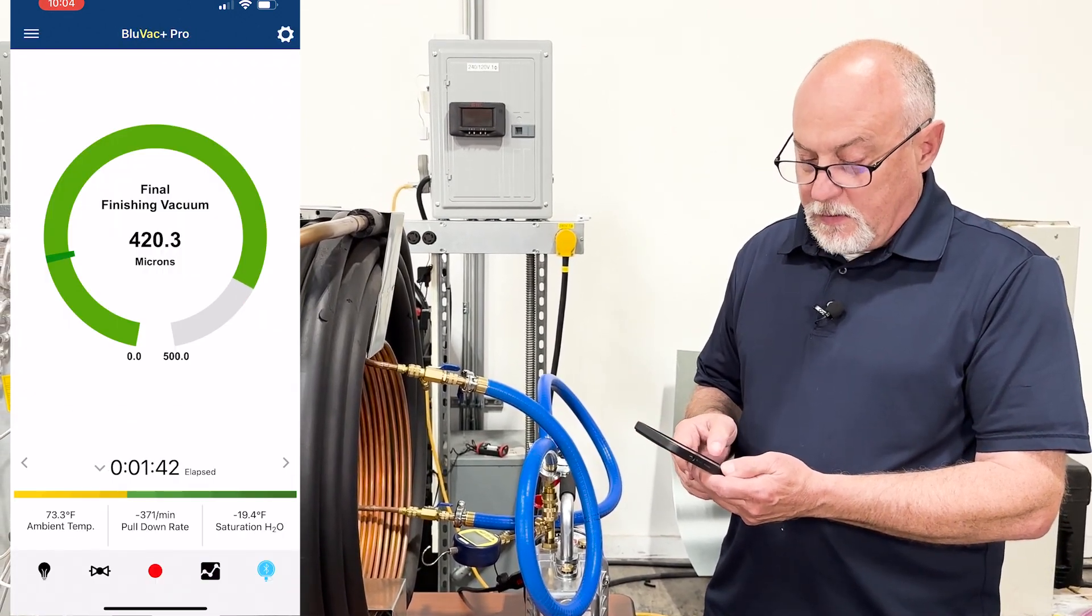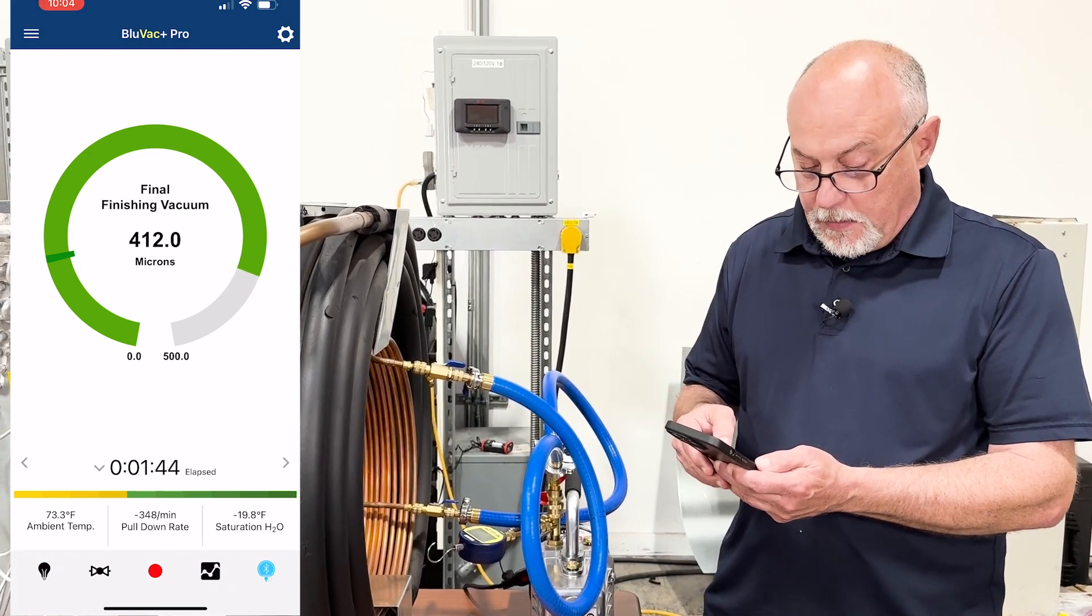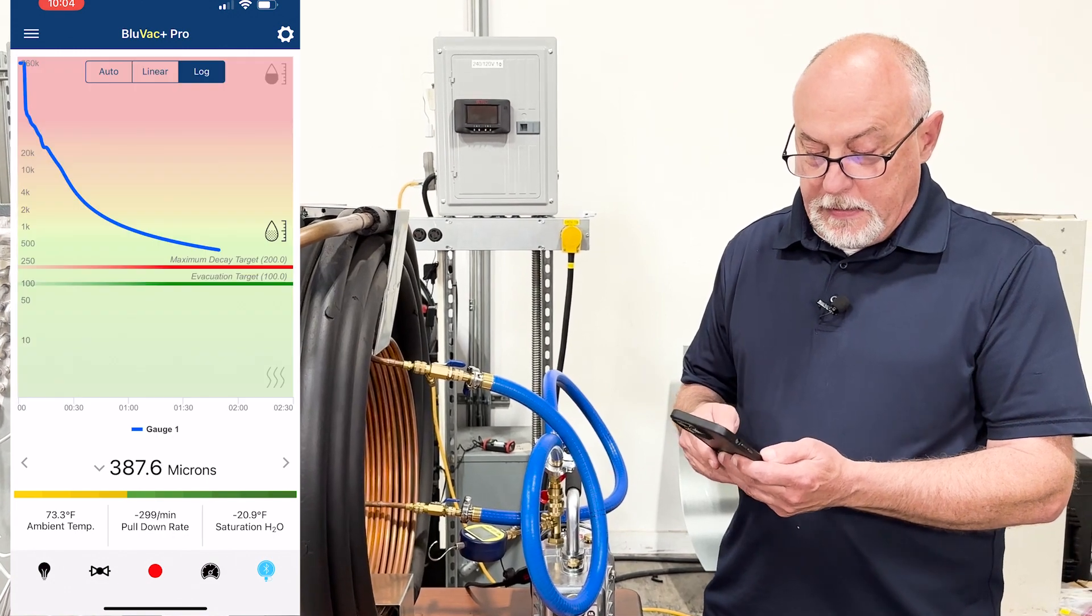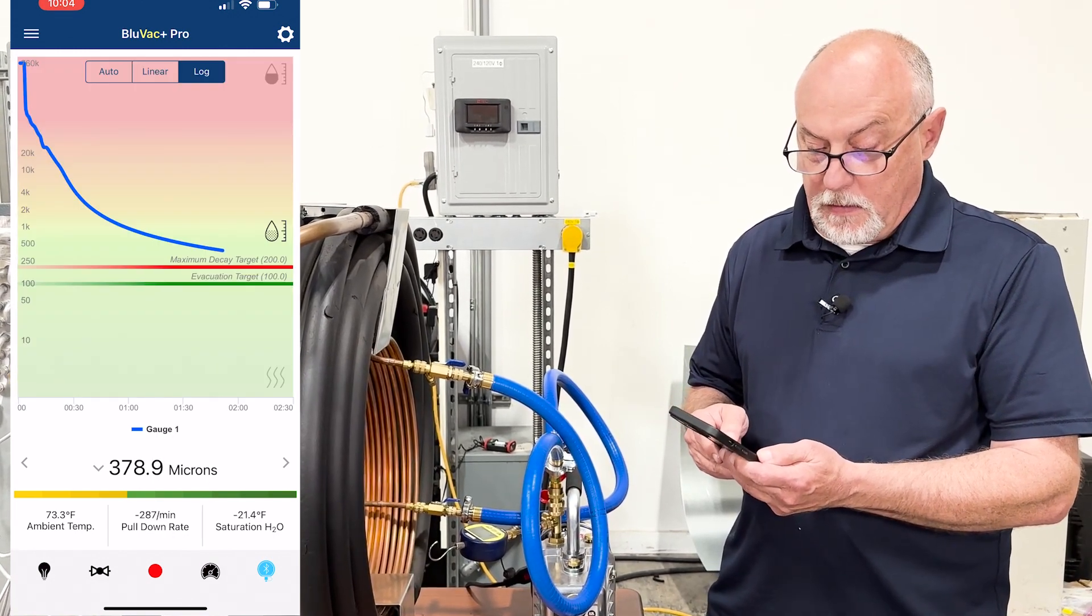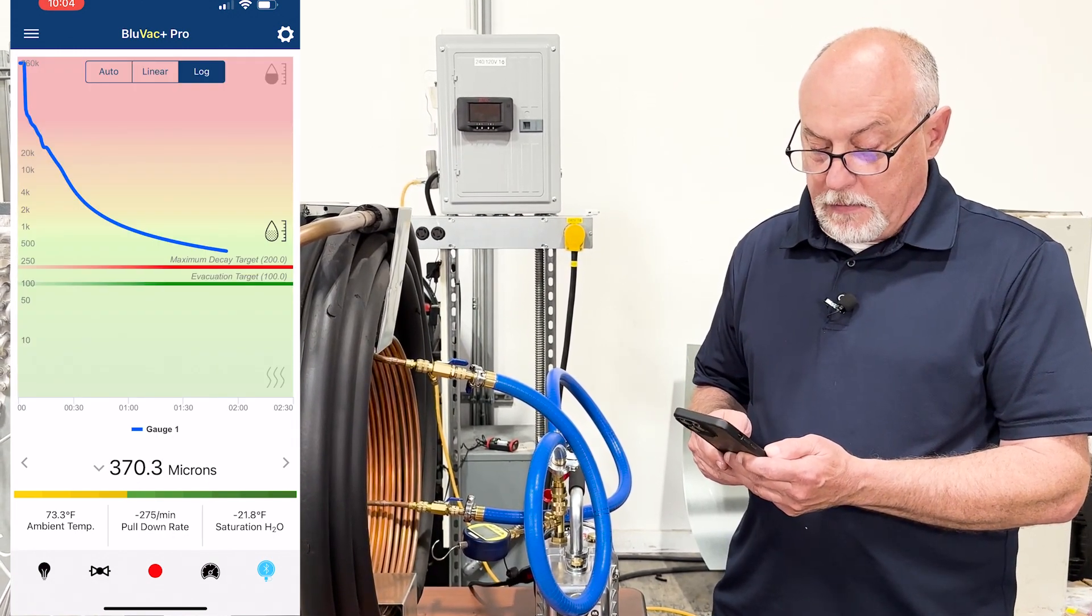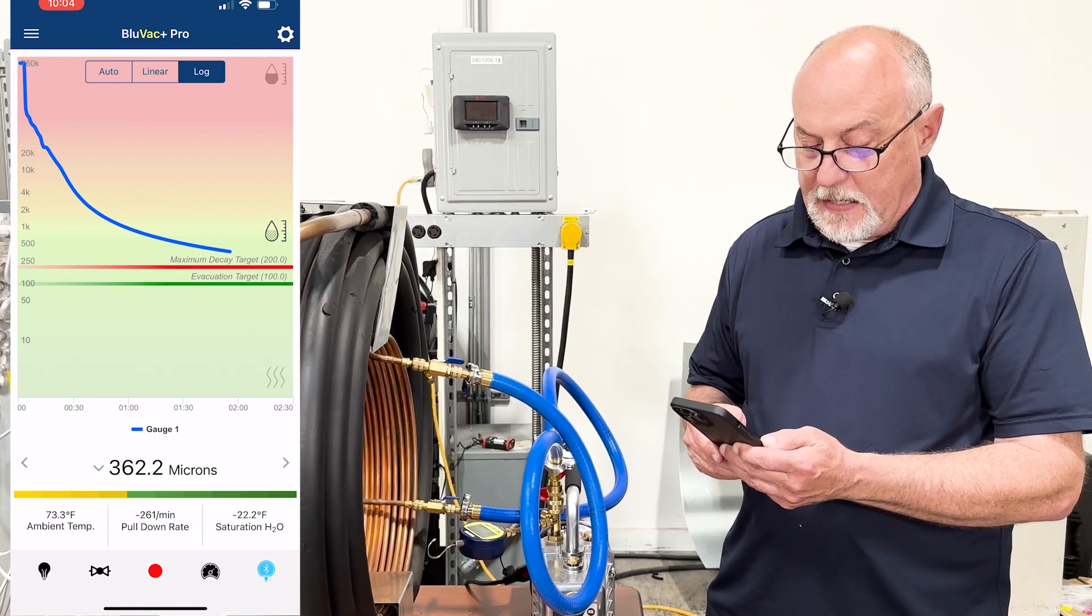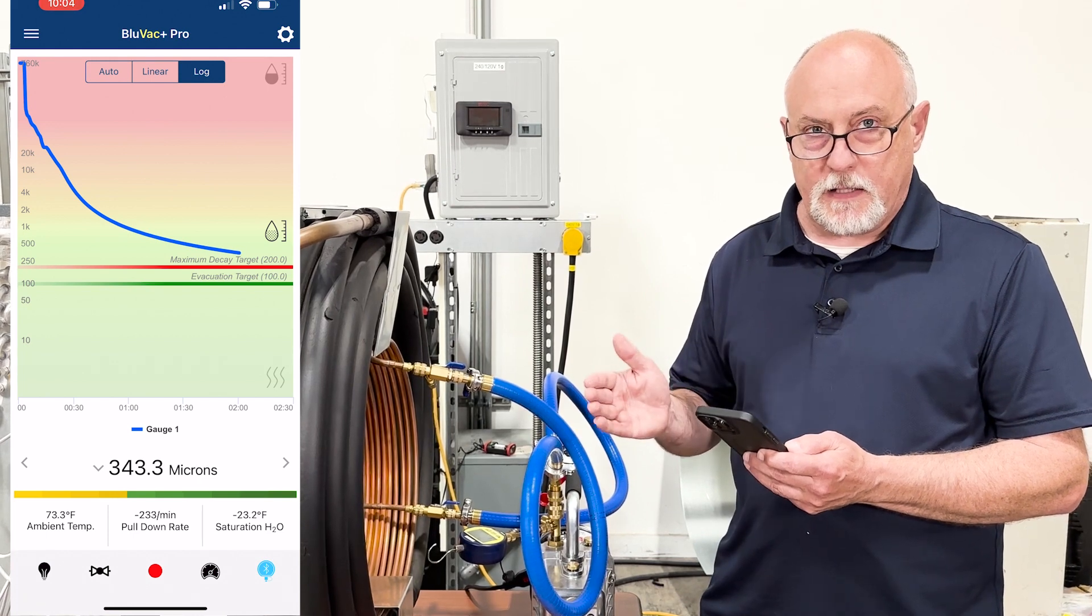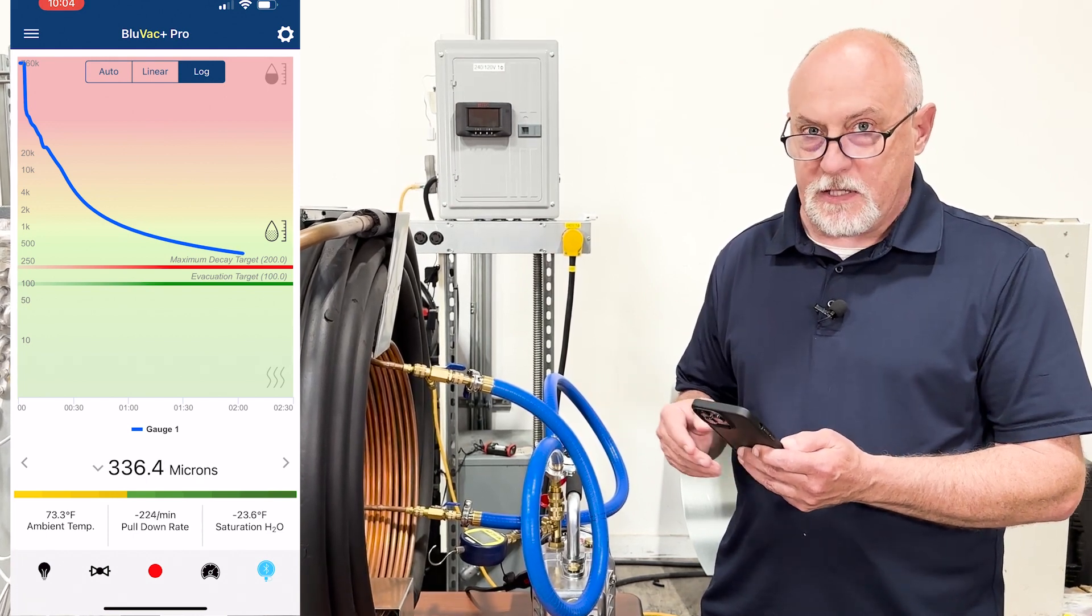So now if I go here, you can see we're already down in a couple minutes here. We're at one minute and 45 seconds. We're already at 400 microns on there. And you can see we're coming down on our graph quite quickly. And we're just about down to our maximum decay target. So we're going to pause here for a minute and let this come down till we hit the targets, and I'll show you what happens next.